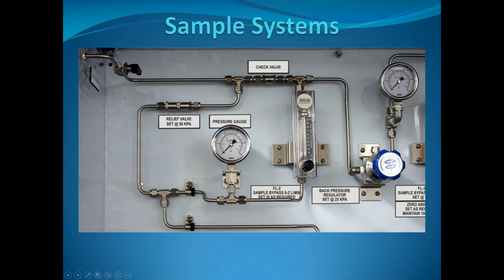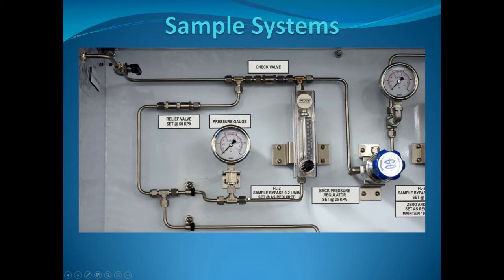Here's a picture of a fairly elaborate yet simple sample system, all contained within a little cabinet. When you have an arrangement like this with all the different conditioning components mounted in a cabinet, they call it a sample conditioning unit. The sample conditioning unit is the part of the sample system that prepares the sample to make it acceptable for the analyzer, which has very specific requirements in terms of temperature, pressure, cleanliness, phase — liquid or gas — and the amount of solids it can tolerate.